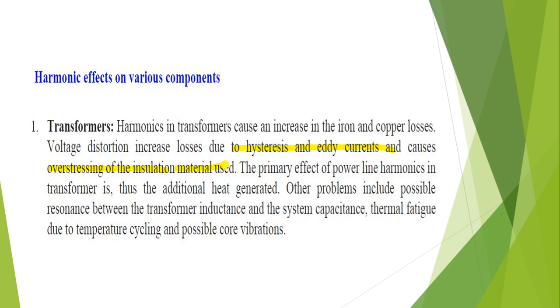Transformer. Harmonics in a transformer cause an increase in the iron and copper loss. We know that voltage distortion increases losses due to hysteresis and eddy current and causes overstressing of the insulation material used. The primary effect of power line harmonics in a transformer is thus the additional heat generated. Other problems include possible resonance between the transformer inductance and the system capacitance, thermal fatigue due to temperature cycling, and possible core vibration.